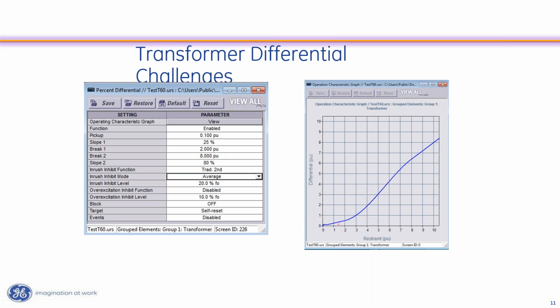Okay, now the other settings that I need to build are the slope differential characteristic. Now there's a few settings that matter there. There is a minimum pickup, and so that's the point right here where the differential current has to be greater than that value before the thing ever operates. And then there is a breakpoint 1 and a breakpoint 2. Now breakpoint 1 is this point right here. Breakpoint 2 is this point right here.